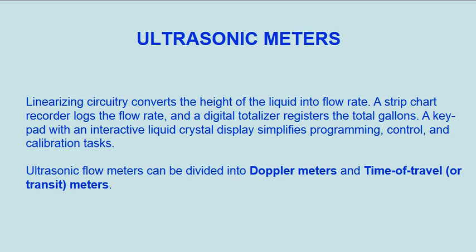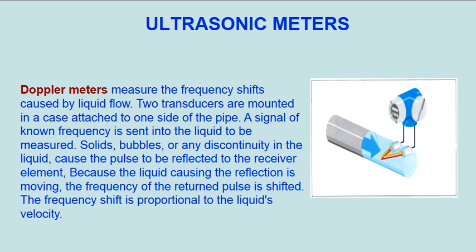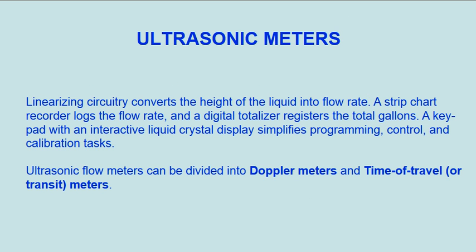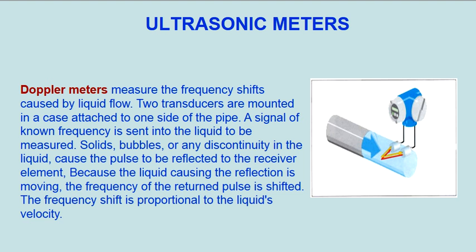Ultrasonic flow meters can be divided into Doppler meters and time of travel, or transit, meters. Doppler meters measure the frequency shifts caused by liquid flow. Two transducers are mounted in a case attached to one side of the pipe.